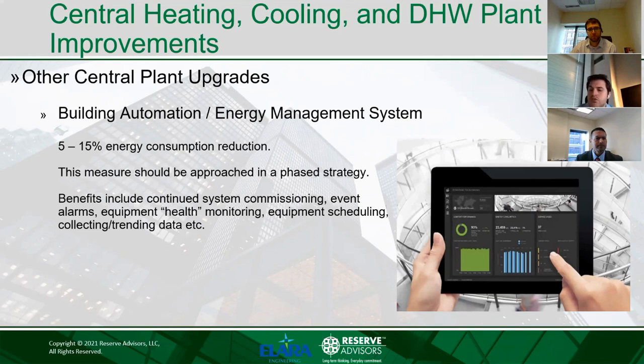It is not the case usually, as the project can be implemented in a phased strategy. Building automation system integration is flexible, and depending on your association's budget, it can be implemented in phases. It allows equipment and monitoring capabilities to be added throughout the life of the building. This flexibility would allow the building to add only the most sensitive HVAC equipment initially and continually add equipment as the association's funding allows later. With implementation of energy efficient control strategies with building automation systems, we would typically expect 5 to 15% overall building energy consumption reduction, which is significant.